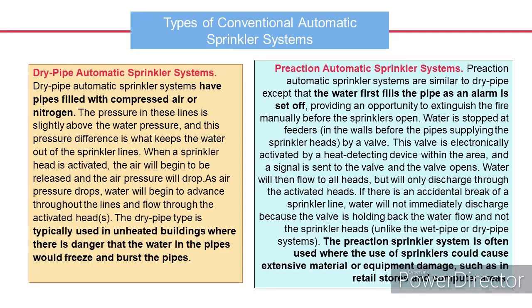Second type is the dry pipe automatic sprinkler systems. Dry pipe automatic sprinkler systems have pipes filled with compressed air or nitrogen. The pressure in these lines is slightly above the water pressure, and this pressure difference is what keeps the water out of the sprinkler lines. When a sprinkler head is activated, the air will begin to be released and the air pressure will drop. As air pressure drops, water will begin to advance throughout the lines and flow through the activated head. The dry pipe type is typically used in unheated buildings where there is danger that the water in the pipes would freeze and burst the pipes.